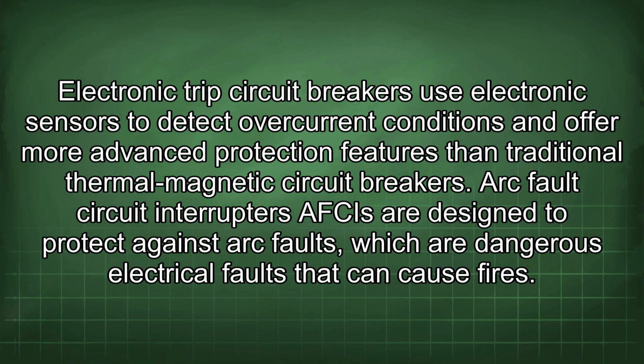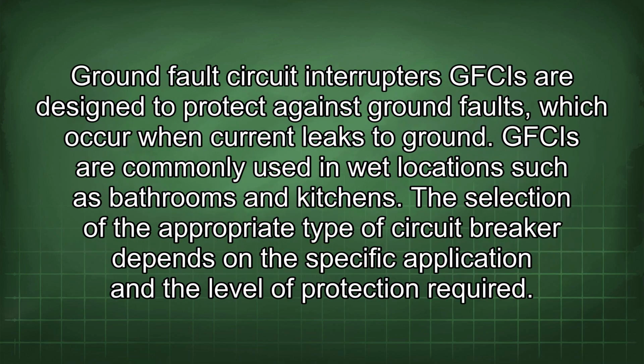Electronic trip circuit breakers use electronic sensors to detect overcurrent conditions and offer more advanced protection features than traditional thermal magnetic circuit breakers. Arc fault circuit interrupters, AFCIs, are designed to protect against arc faults, which are dangerous electrical faults that can cause fires. Ground fault circuit interrupters, GFCIs, are designed to protect against ground faults, which occur when current leaks to ground. GFCIs are commonly used in wet locations such as bathrooms and kitchens. The selection of the appropriate type of circuit breaker depends on the specific application and the level of protection required.